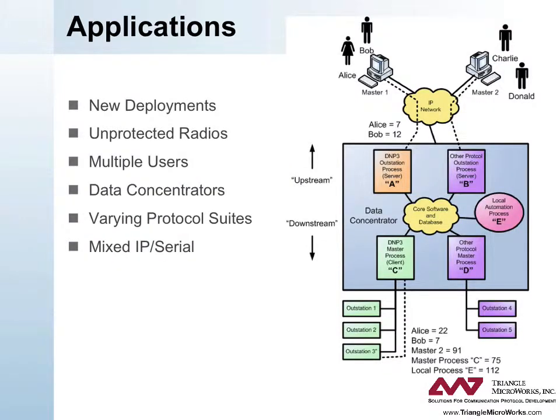DNP3 Secure Authentication is suited for the following types of applications. New deployments: because this is an addition to the DNP3 protocol itself, it will require new software or firmware at both ends of the connection. Therefore, it may be most convenient to deploy DNP3 Secure Authentication in new networks and investigate other solutions for legacy systems. Unprotected radios: radio systems with serial link inputs that are not authenticated or encrypted represent one of the most vulnerable types of DNP3 deployments. Deploying DNP3 Secure Authentication permits these networks to be secured without hardware changes.